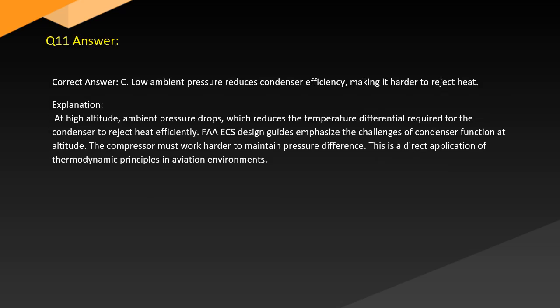Answer. Correct answer C. Low ambient pressure reduces condenser efficiency, making it harder to reject heat. Explanation. At high altitude, ambient pressure drops, which reduces the temperature differential required for the condenser to reject heat efficiently. FAA ECS design guides emphasize the challenges of condenser function at altitude. The compressor must work harder to maintain pressure difference. This is a direct application of thermodynamic principles in these environments.